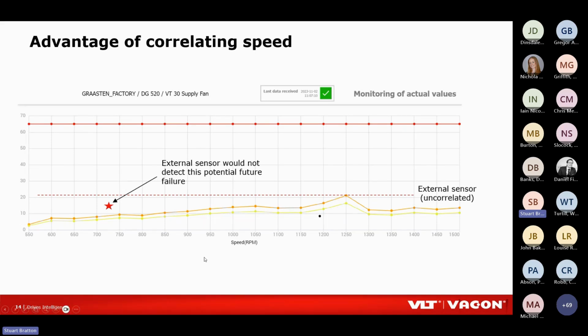But the drive, obviously, has correlated this data against speed. It's capable of saying, well, actually, at 725 RPM, this 15 millimeter vibration level is unusual. That's a problem. And it'll either throw a warning or an alarm, depending on how we've configured the drive.